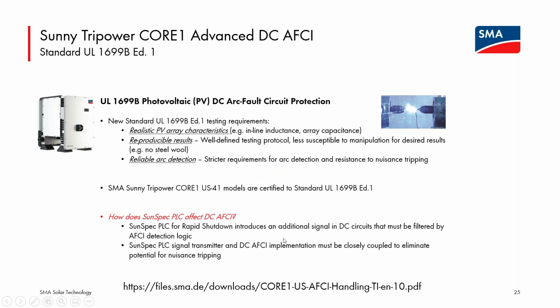The other functionality that the recent firmware unlocks in the CORE1 is again related to how the system handles arc fault detection. It used to be that when AFCI detection was required in the National Electric Code, code specifically called out that a manual restart of the system was required anytime an arc was detected. That can be cumbersome if the site is fairly remote. 2017 code in the United States allowed for the ability to restart automatically from an arc event, if the incident energy of the arc was under a certain threshold and the extinguishing time was short enough. Code then explicitly allowed it.